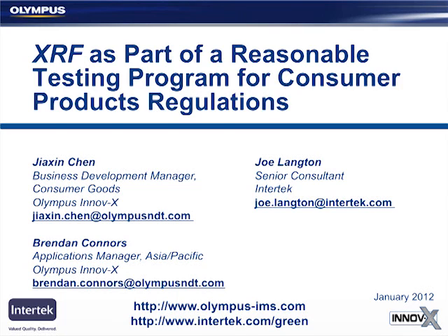So the first thing I would say with testing packaging materials is if your sample is very thin, you're testing cardboard or plastic wrapping, try to make a thicker sample as much as possible, and you can do that just by stacking multiple layers or wrapping it up a bunch of times. You may see a great improvement on the results that you're seeing.